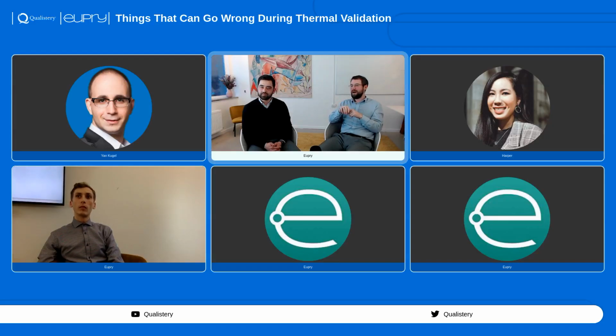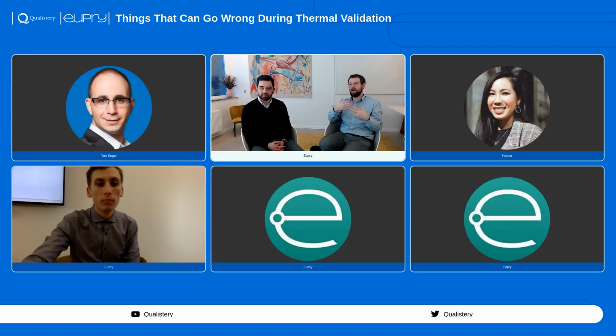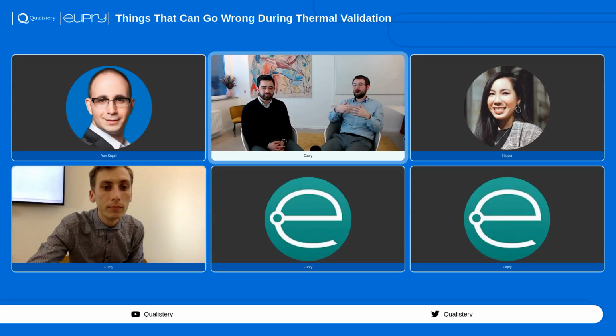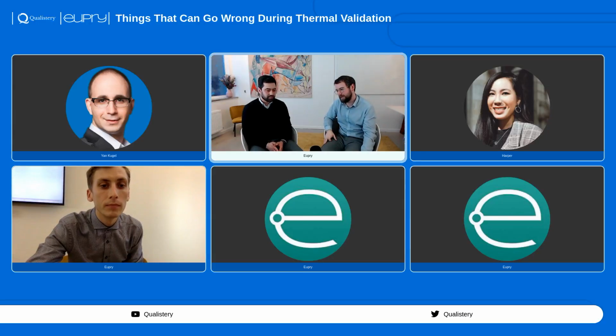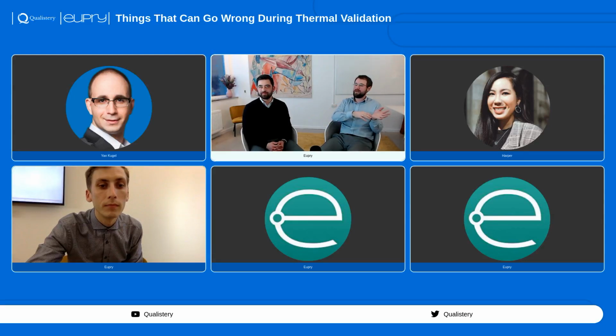It's often related to averages and peak temperatures, peak high temperatures and peak low temperatures. So the data analysis is quite simple. What is not so simple is making sure, for example, that you have all your data points. If you have some systems that show graphical representations of data, how do you make sure that you have the full set of data? Normally, when you write a protocol, you would have a requirement for how often you need to measure temperature. Let's say every 5 minutes. That's a very typical limit for how often you need to have data samples. How do you make sure that you have every 5 minutes and that you're not missing anything in the middle?